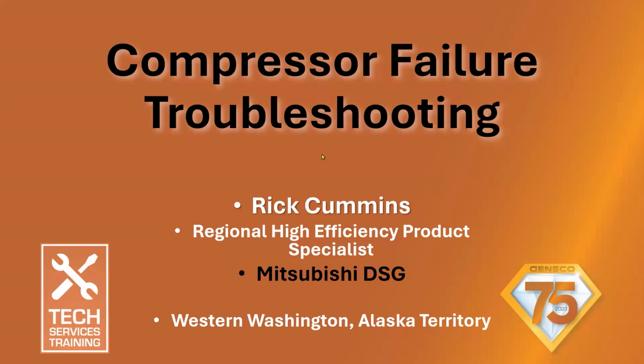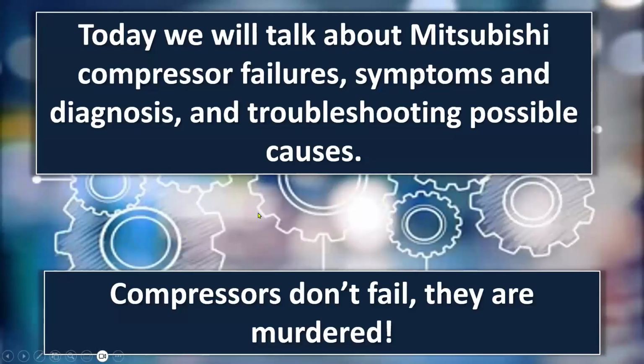Okay. So, to start off, we will talk about compressor failures, symptoms that you will see when the compressor has failed, troubleshooting possible causes of the compressor failure. And someone wrote this little term I saw this past fall: compressors don't fail, they are murdered. And it's fairly true. They generally don't have manufacturing defects that will cause them to fail. It's all about the job itself. Something in the job has caused it to fail.